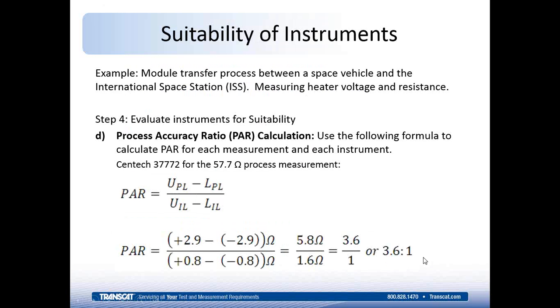So that's another step in the process. We've confirmed so far that the parameters can be measured with each of the instruments, and now we're looking at our process accuracy ratio to determine whether that instrument is accurate enough to make the measurement of the process. The reason we want to look at an accuracy ratio is to determine whether that tolerance of the instrument is too wide or too close to the tolerance of the process that we're measuring. So it needs to have a healthy ratio. What determines the healthy ratio? Well, that really is the decision of the manufacturer of that component to say what that healthy ratio is. But for most applications, a 4-to-1 ratio is typically what you're looking for, or better.